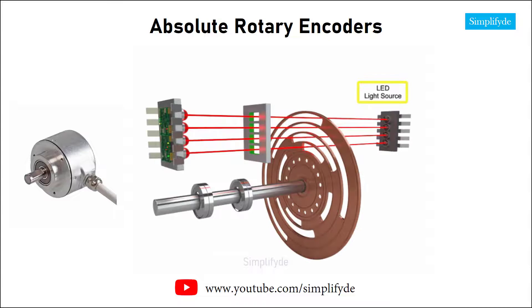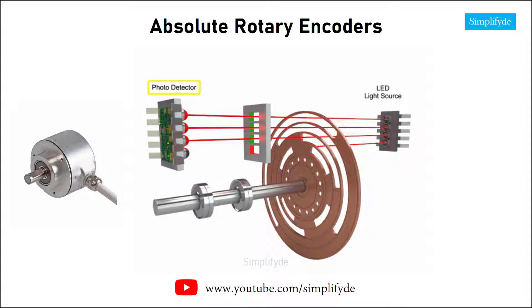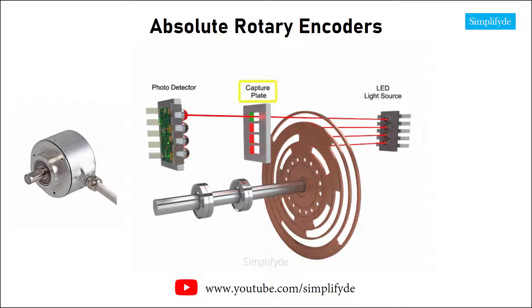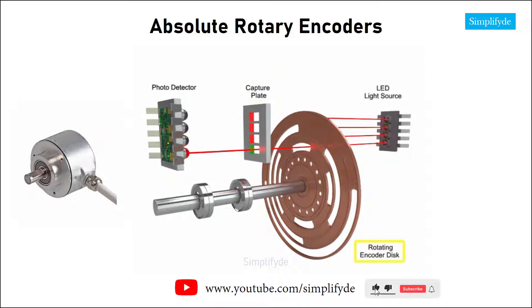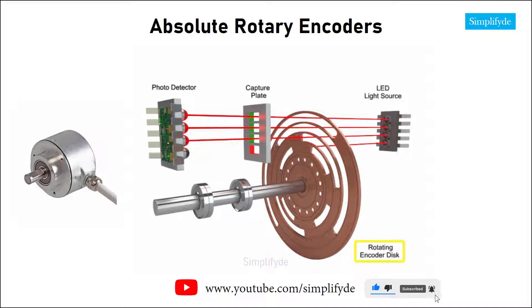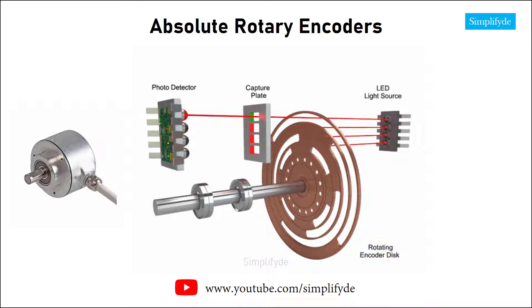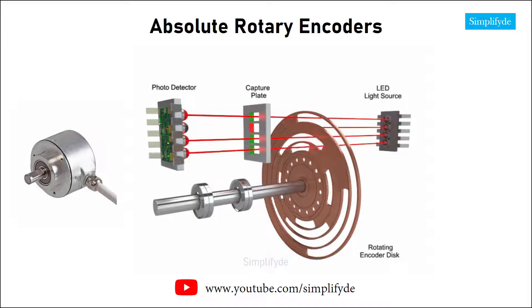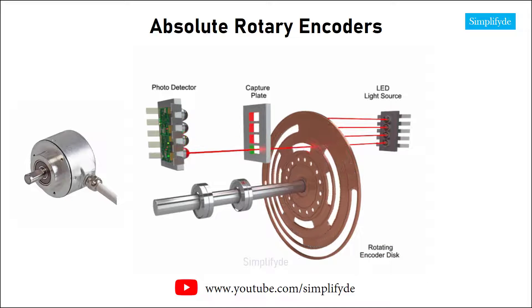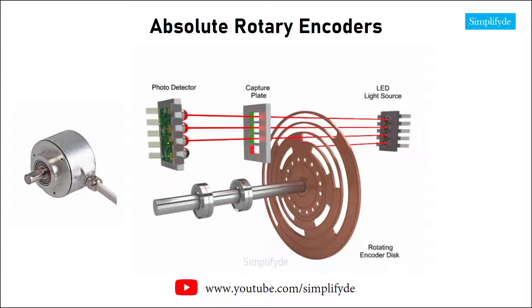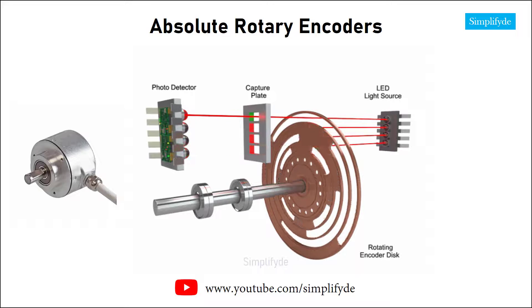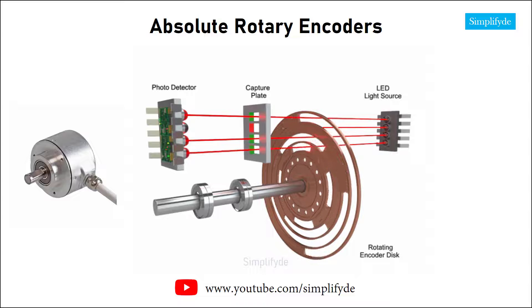A light source located on the opposite side of the photocells passes light through a capture plate. As the encoder disk rotates, light is either transmitted or blocked according to the pattern. The received light provides a four-bit word that indicates the position of the actuator or device the encoder is mounted to.